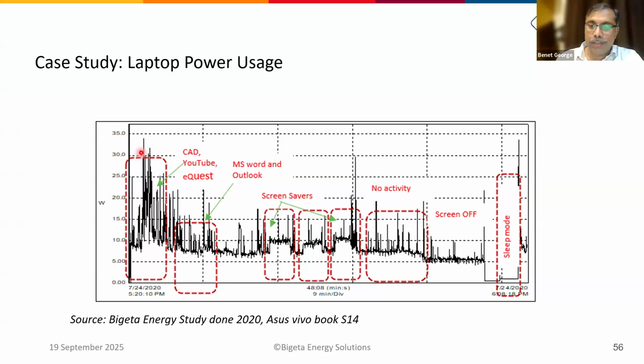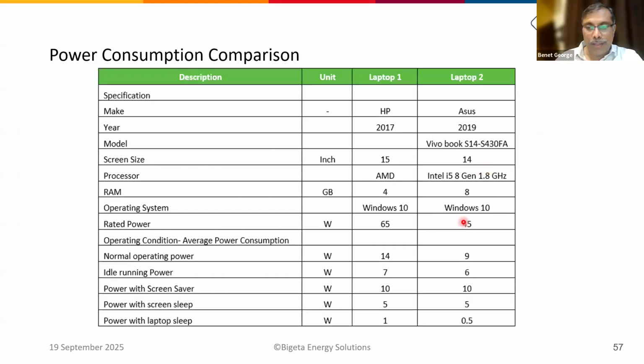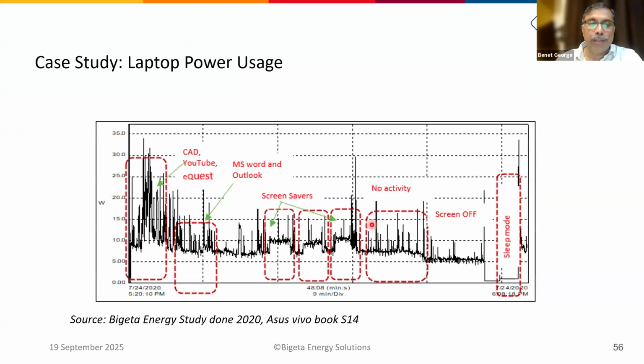the rated power was, in this case, you can see 45 watt. In many cases, when you're purchasing a UPS, we multiply 45 watt into 100 laptops. Then we find a capacity. Then accordingly, we think, okay, we need a very large capacity UPS. But in fact, in actual condition, it may be consuming only 1/3 of its rated condition. And you can also consider the diversity factor.